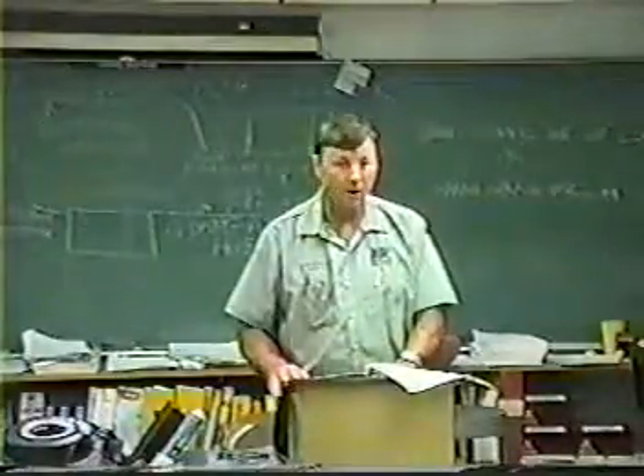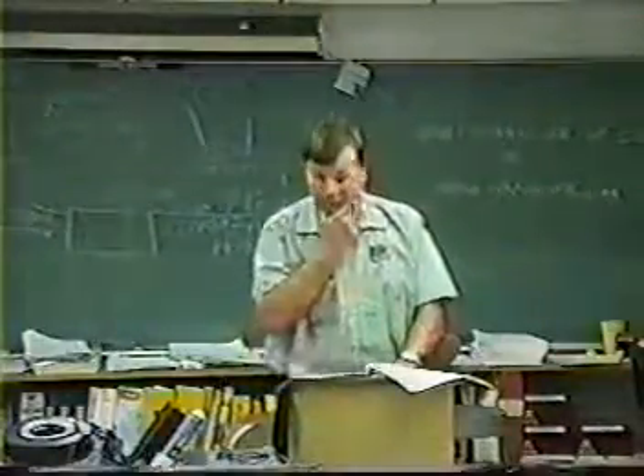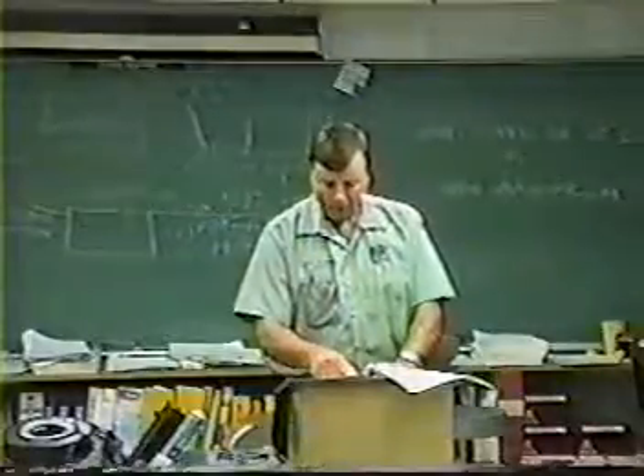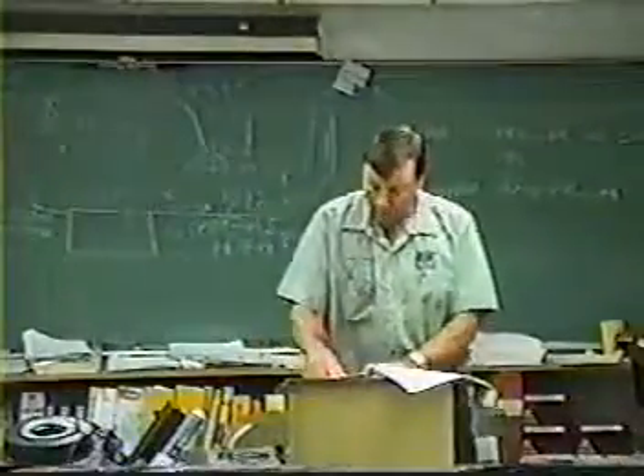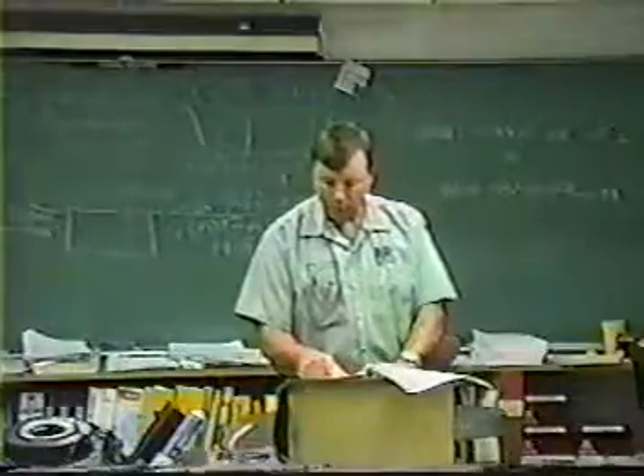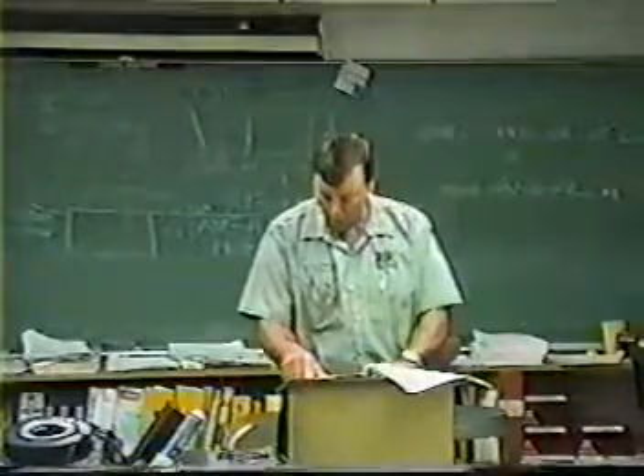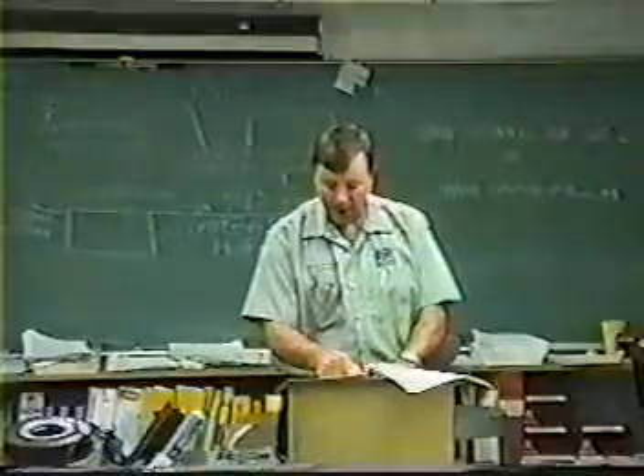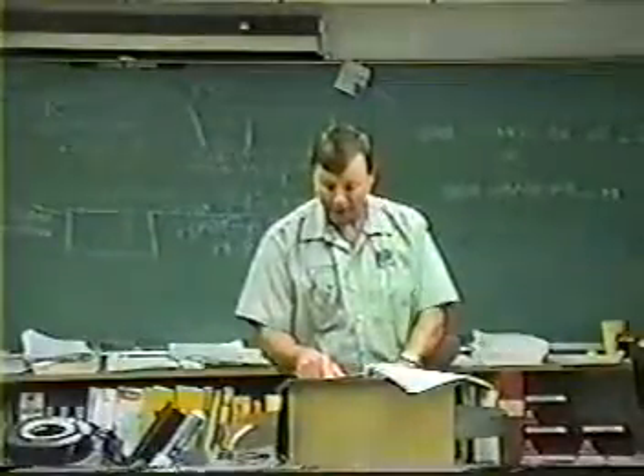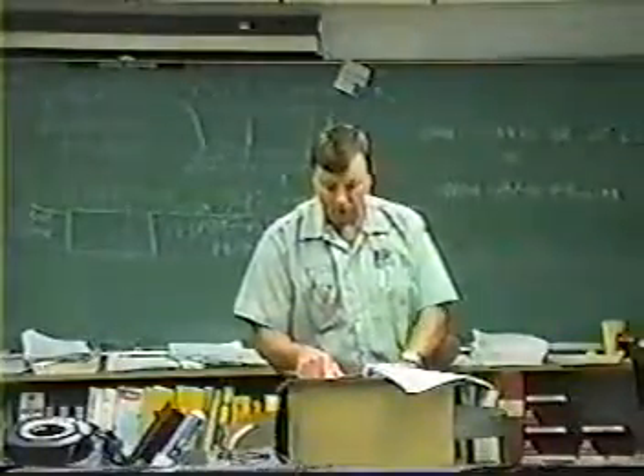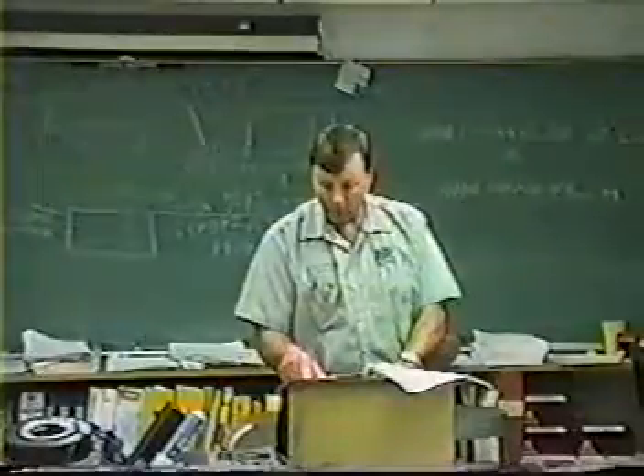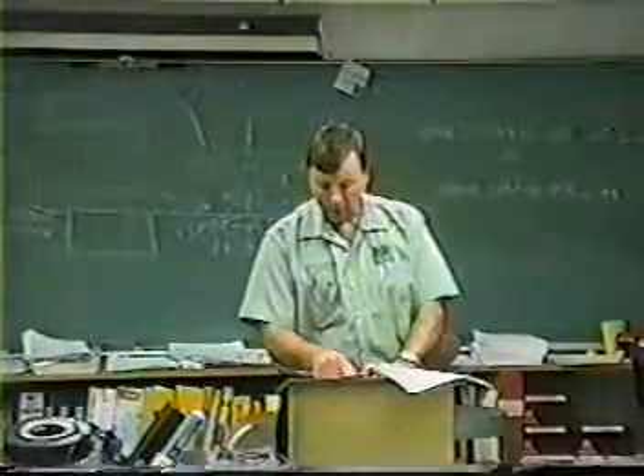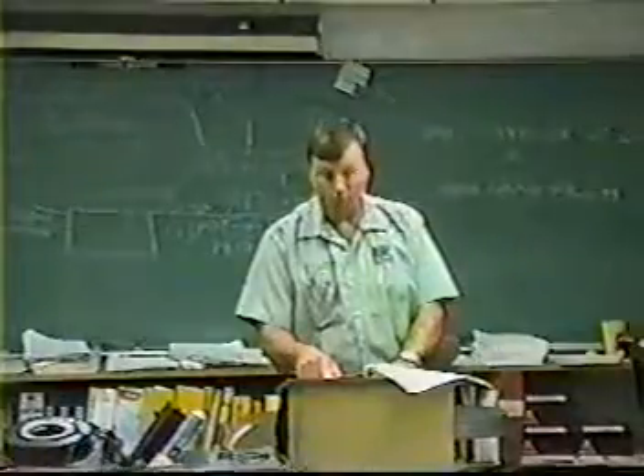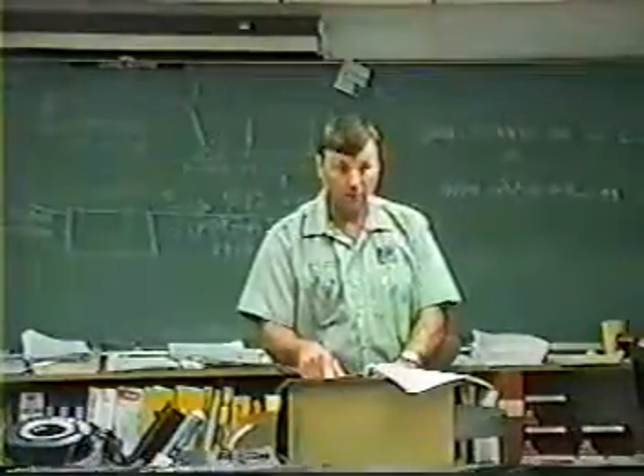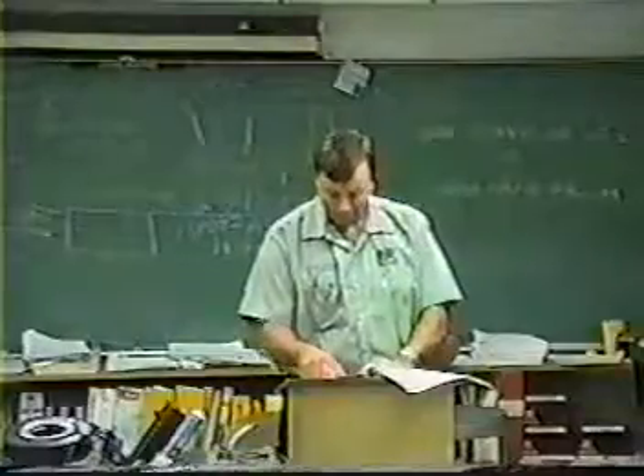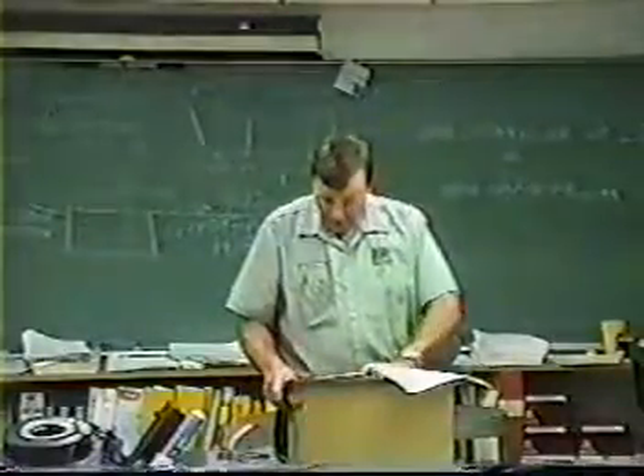We got to sit down and figure out and know them and know exactly where to go back and look this information up. Our commercial and industrial procedure. Commercial and industrial process refrigeration appliances that contain more than 50 pounds of refrigerant must be repaired when the annual leak rate exceeds 35%, which is good common sense to know. If it's more than 50 pounds, and you got an annual leak rate of 35%, you're losing a bunch of refrigerant, guys. See, that's a key point in getting it repaired.